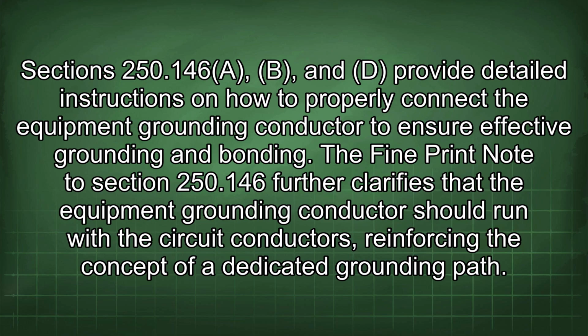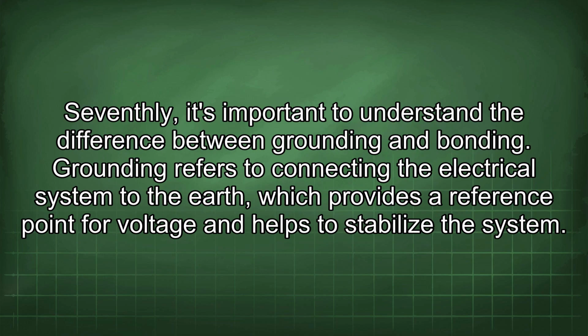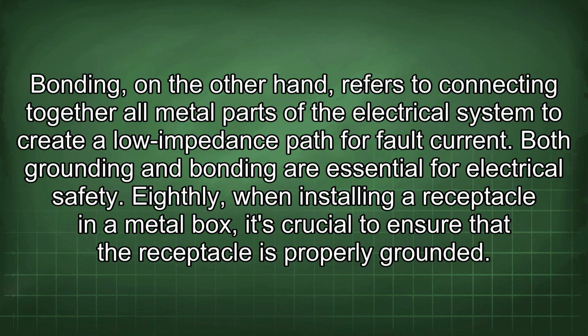Seventhly, it's important to understand the difference between grounding and bonding. Grounding refers to connecting the electrical system to the earth, which provides a reference point for voltage and helps to stabilize the system. Bonding, on the other hand, refers to connecting together all metal parts of the electrical system to create a low impedance path for fault current. Both grounding and bonding are essential for electrical safety.